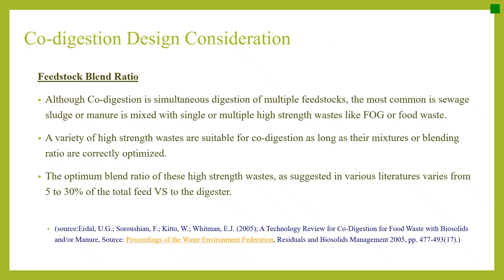Let's move to codigestion design considerations. Codigestion is a new trend — the simultaneous digestion of multiple feedstocks, most commonly wastewater sludge or manure mixed with single or multiple high-strength wastes like FOG or food waste. The optimum blend ratio of high-strength waste as suggested in the literature varies from 5 to 30 percent of the total feed VS to the digester — meaning the VS contribution from high-strength waste should not exceed 30 percent of the total feed VS.